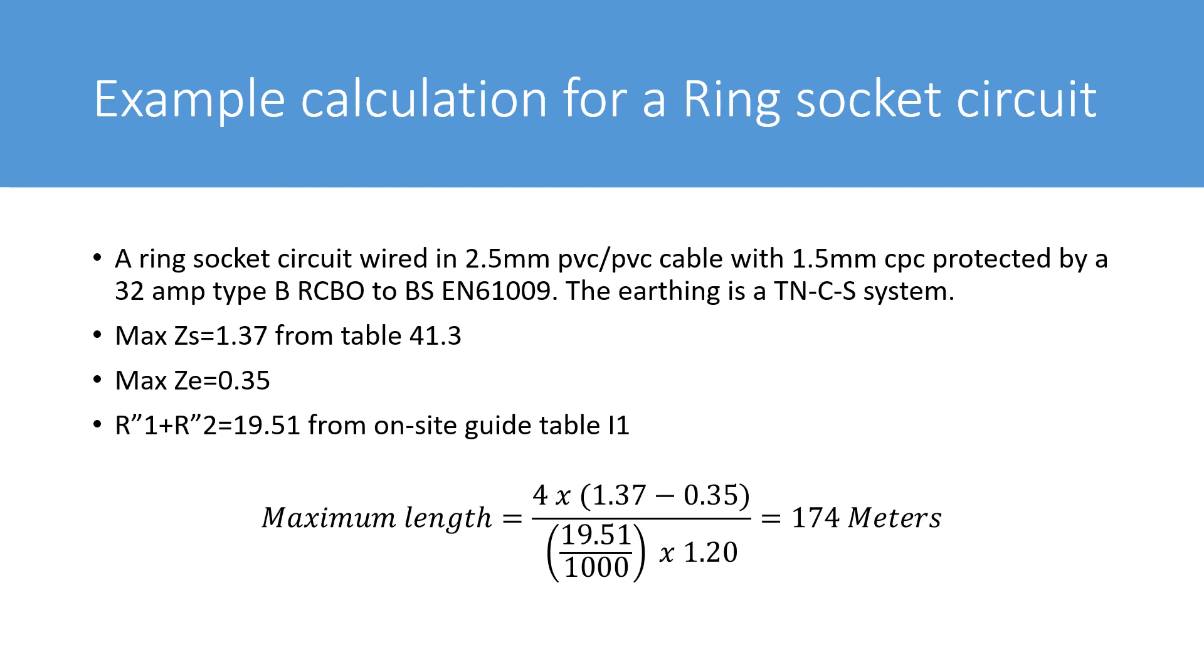The maximum ZS for the protected device is 1.37 and that's from table 41.3. The maximum ZE again is 0.35 because it's a PME system. And then the tabulated value for R1-R2 again is 19.51 and that's from the on-site guide table I1.